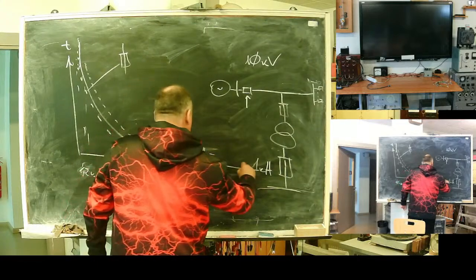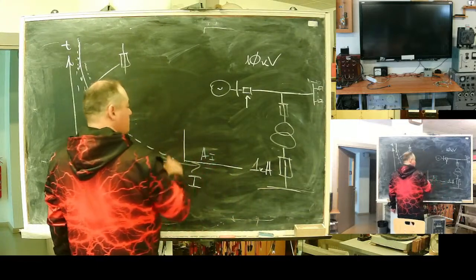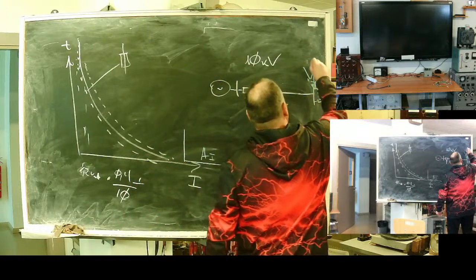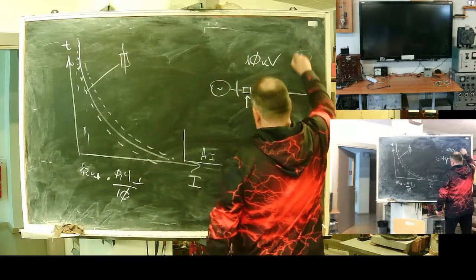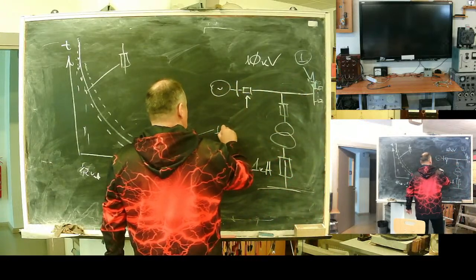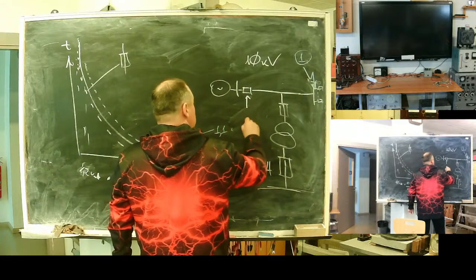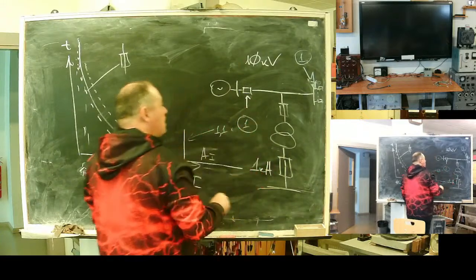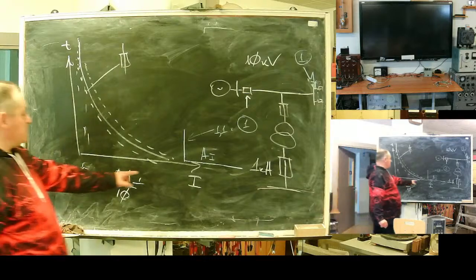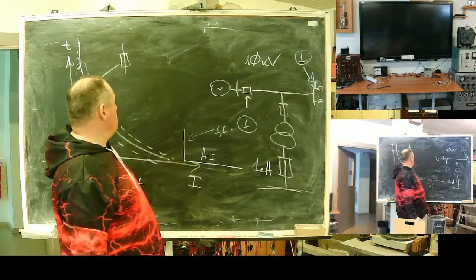A1, the instant zone. Its start current, this point, is roughly 1.1 multiplied by fault current number 1, the three phase fault at the next bus. Here is the trip current of my instant zone.